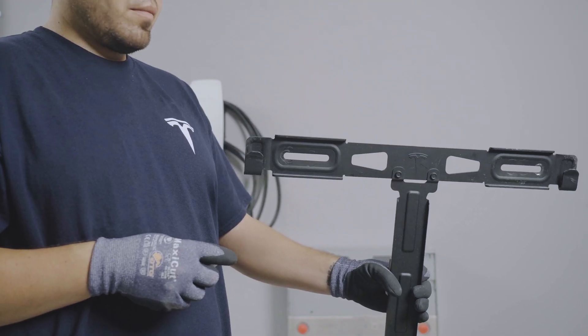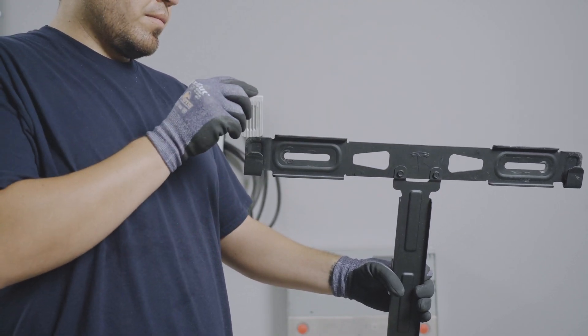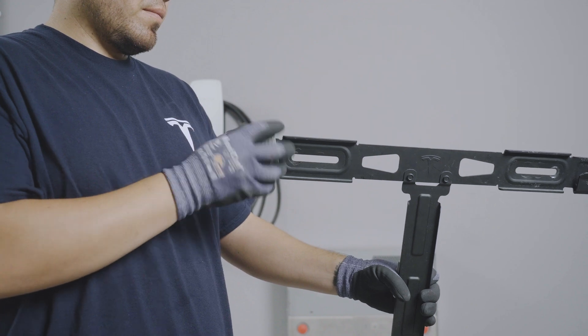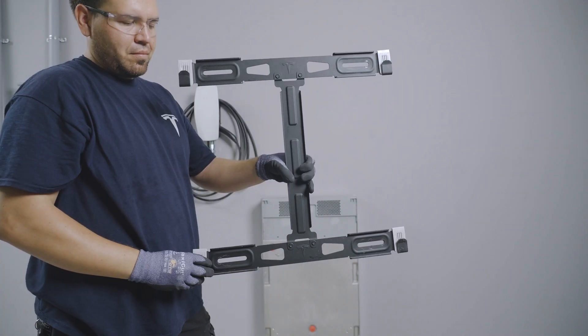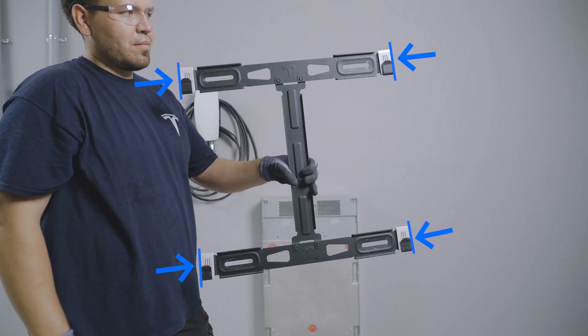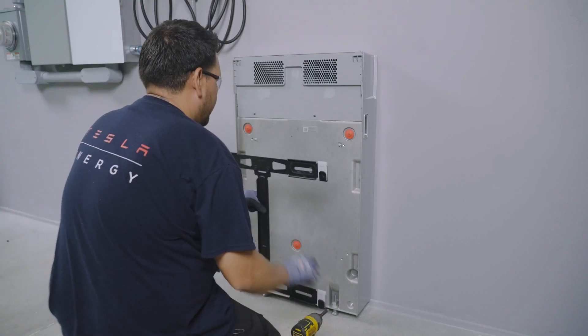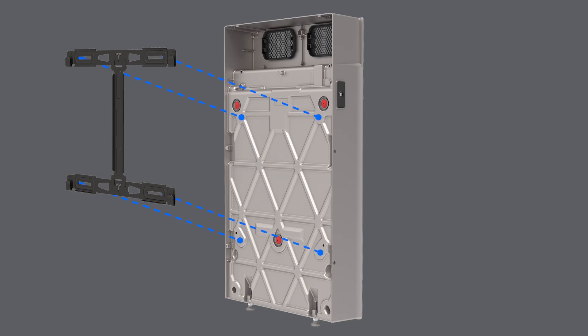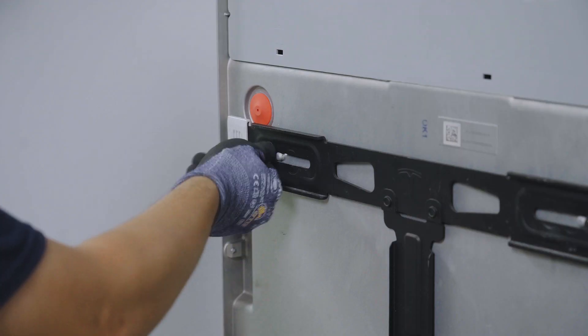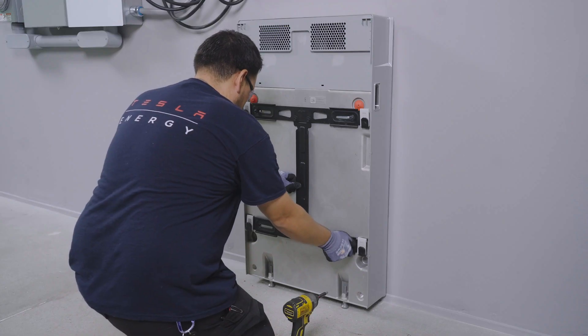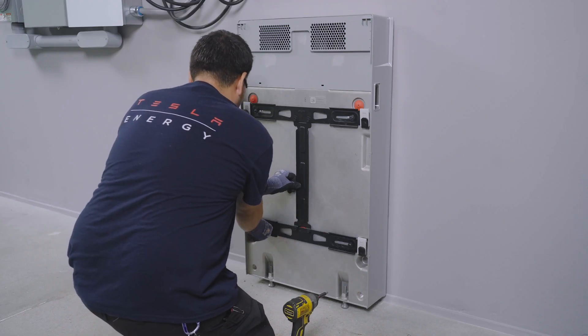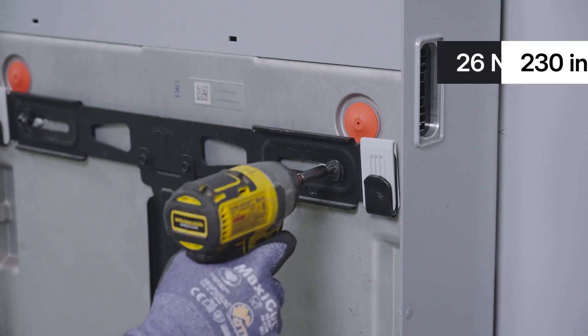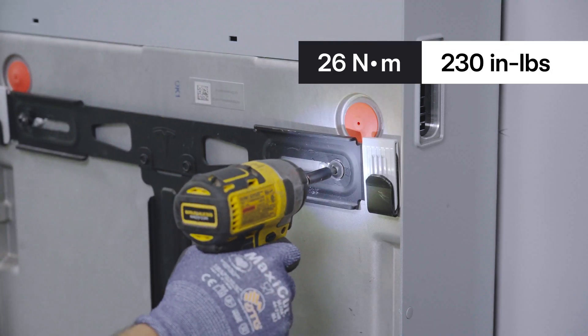Grab the mounting bracket for the next Powerwall in the stack and place the four shims from the accessory kit over each of the four corners, aligning the shim with the edge of the bracket. Hold the bracket in place, aligned over these four threaded holes. Hand start each of the four T40 bolts from the accessory kit to fasten the bracket to the enclosure, then torque to the listed specification.